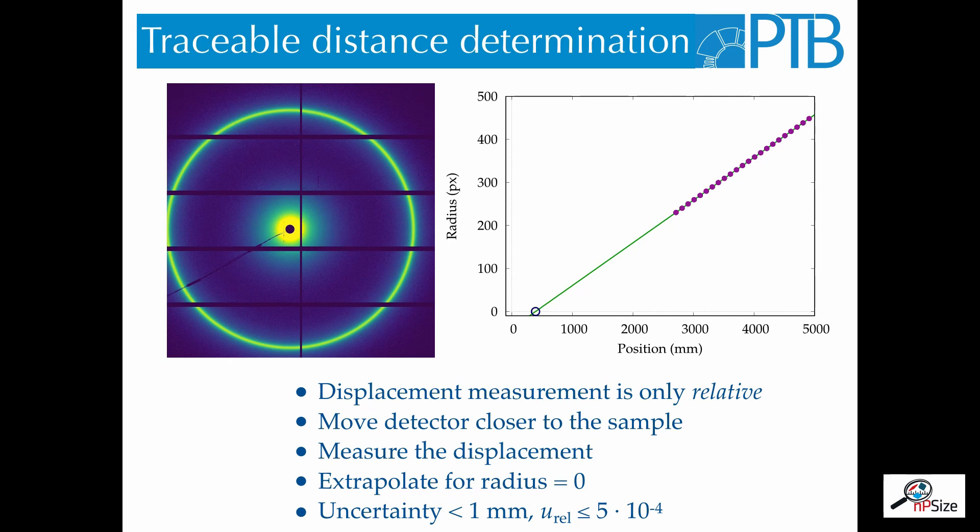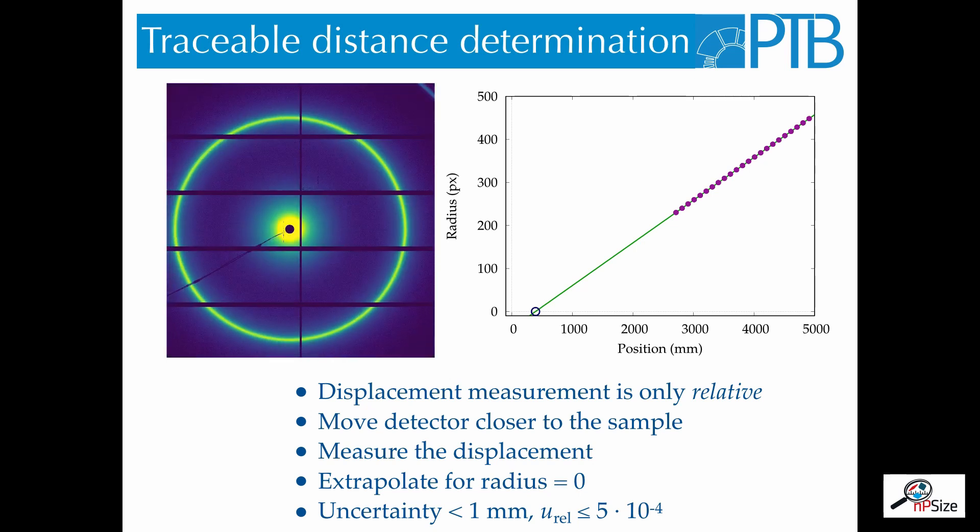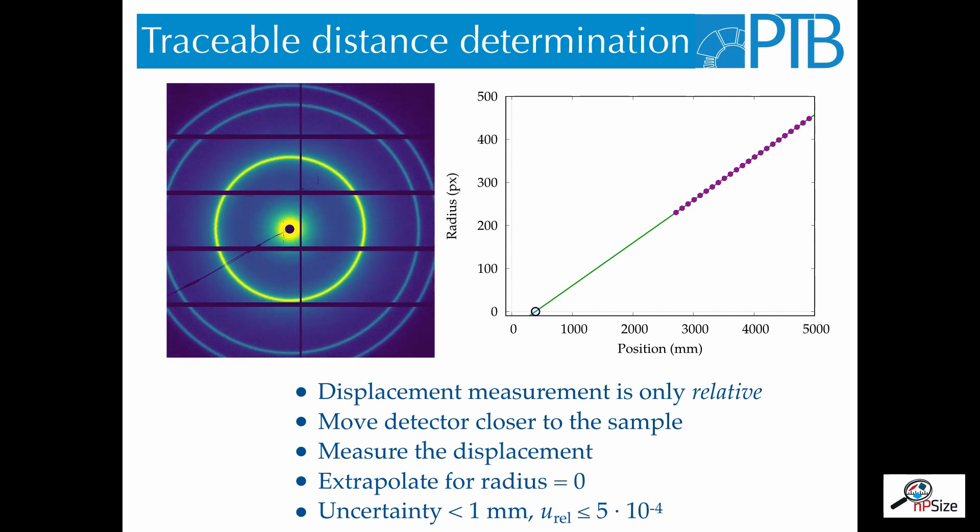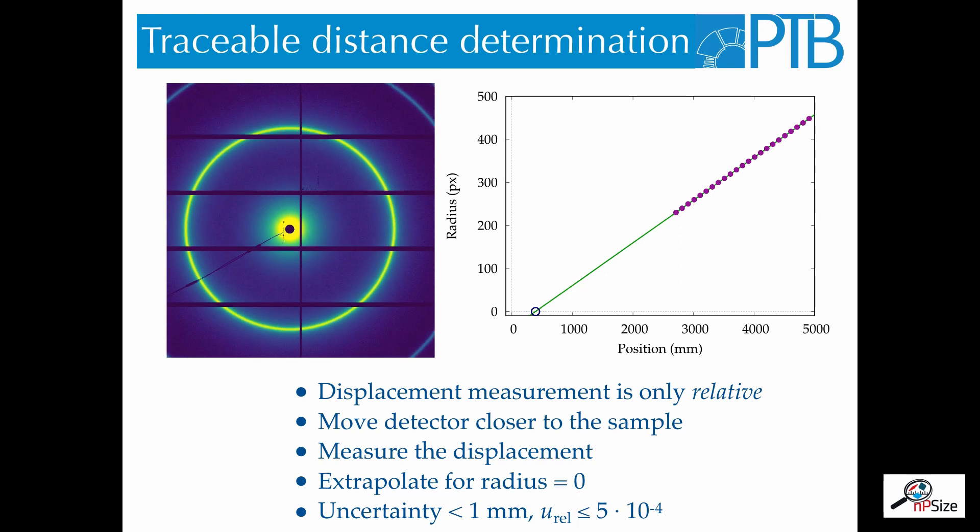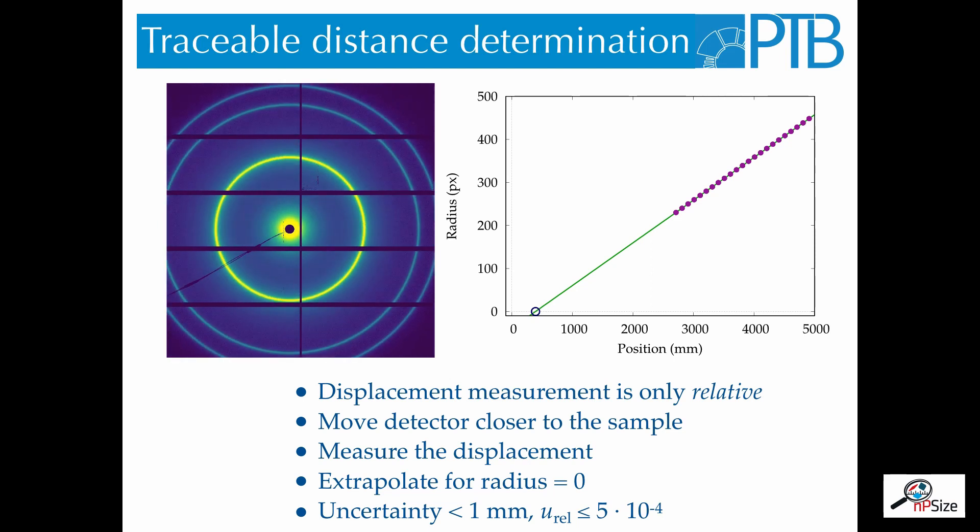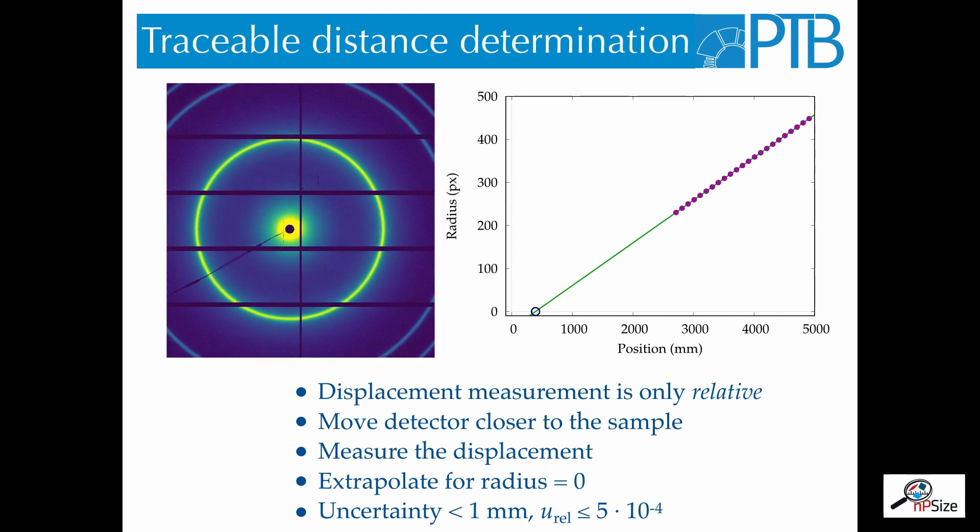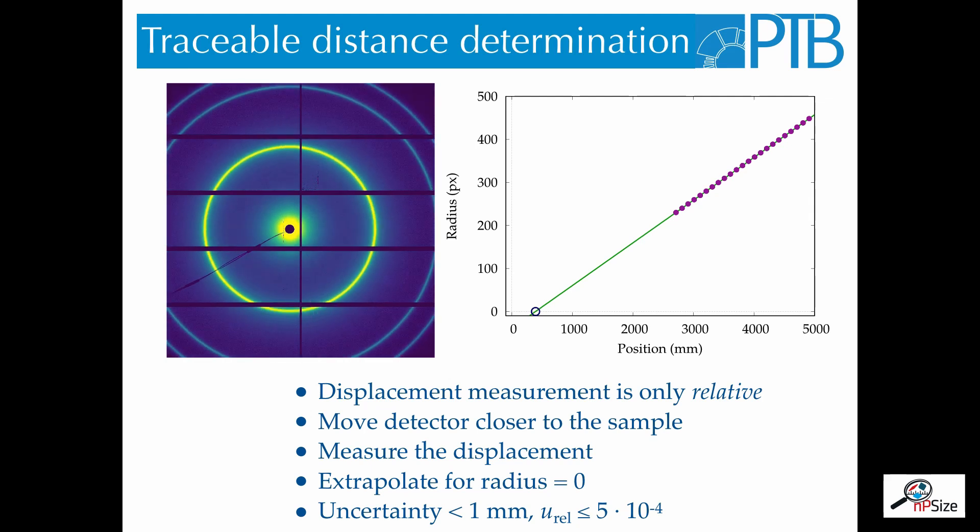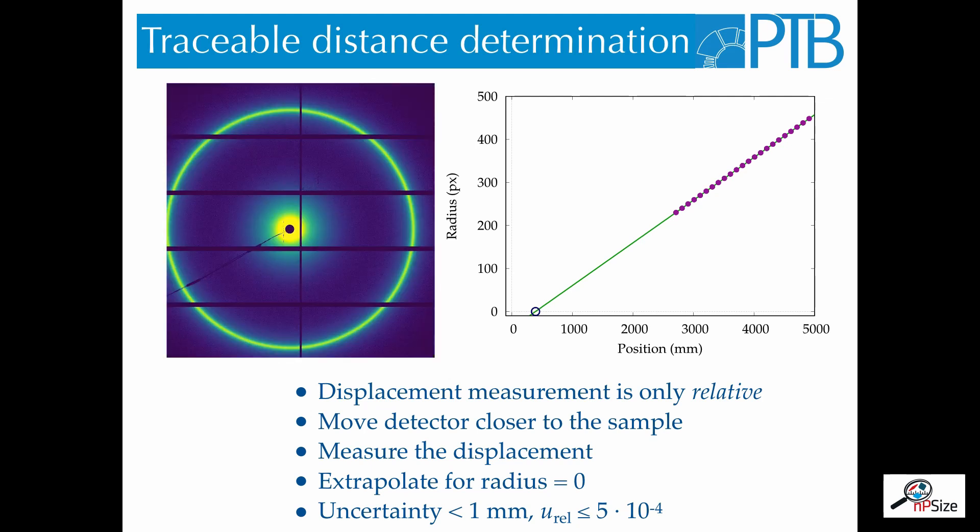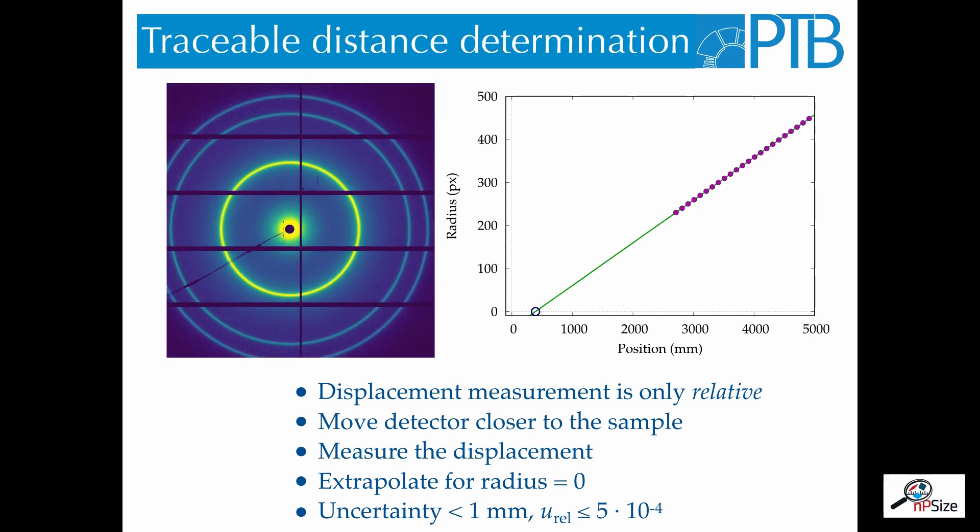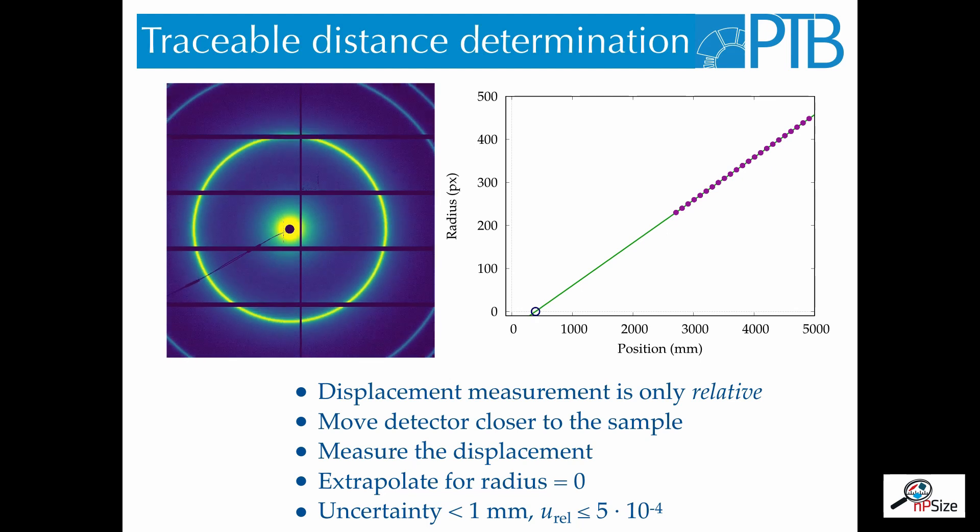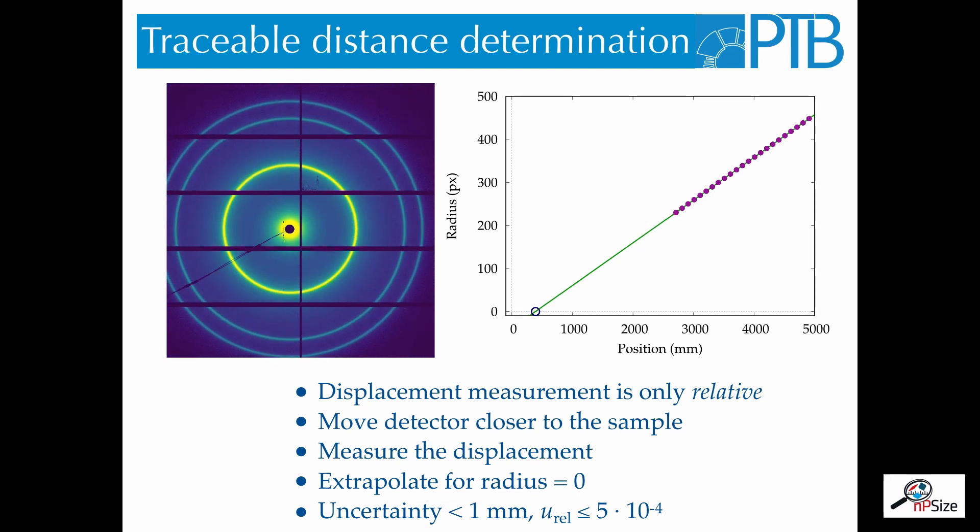On the left-hand side, you see the scattering pattern of a standard sample, which has a very pronounced ring. We then move the detector closer to the sample, therefore the ring shrinks, changes its size. And when we measure the radius of the ring and the displacement of the detector, we can compute the absolute position. On the right-hand side, you see the radius of this ring versus the position of the detector. And by fitting a straight line through these positions and extrapolating to the position where the radius would be zero, we get the total distance between detector and sample with an uncertainty less than one millimeter, which is a relative uncertainty of 5 times 10 to the minus 4.